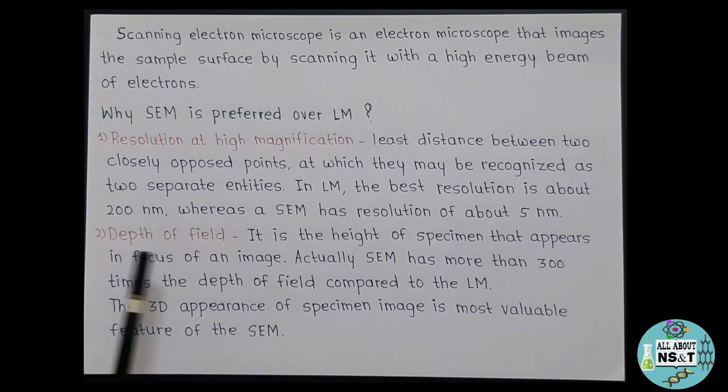Then talking about depth of field. Now what is this depth of field? It is the height of specimen that appears in focus of an image. Actually, SEM has more than 300 times the depth of field compared to the light microscope. This means that great topographical detail can be obtained using SEM. Also, the 3D appearance of specimen image is the most valuable feature of the SEM. This is because even at low magnifications, such 3D images can give much more information about a sample which is otherwise not possible with the light microscope.